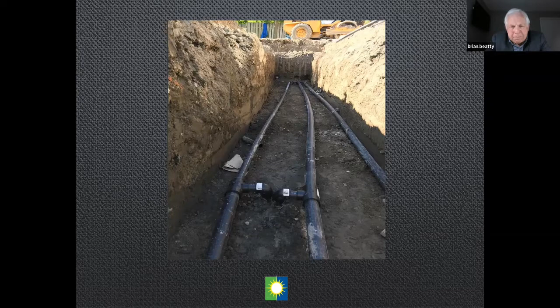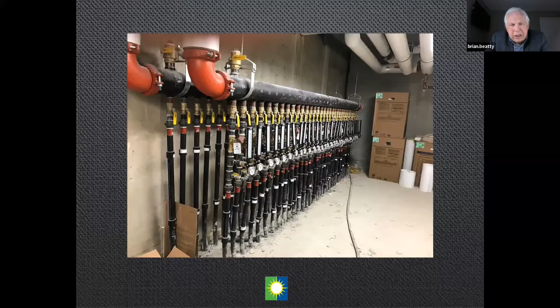Then all that piping is brought into the building. And this is a key integral part of what you see inside a building for a closed loop system. 2 manifolds, those 2 big pipes at the top, and all the piping coming up from the boreholes below. Each one of those pipes that comes up into the manifold will be connected probably to about 10 different boreholes. So you just multiply the number of pipes you see there. There could be 15 or so times 10, that'd be maybe 150 boreholes in this particular example. And the water in the manifold goes into the building through heat exchangers. Next slide.